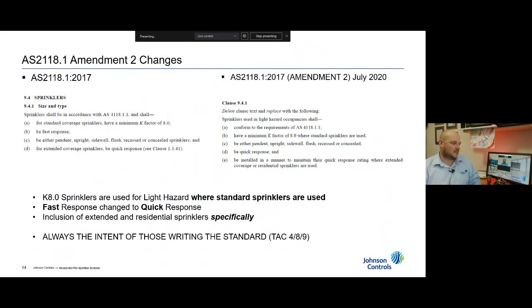So the standard, the 9.4.1 clause changes. Now this has been a little bit of controversy here, because what 9.4.1 says is that for standard coverage sprinklers, they must have a K factor of 8.0, which is our standard commercial sprinkler. And what has happened is a number of people have said, well, if you're going to be using these in a residential application, you can't use residential sprinklers because they have a K factor of 7. That was never the intent of this clause. And so you see on the right hand side there that it has been amended so that they do have a K factor of 8 where standard sprinklers are used. And we've added a paragraph there that says they are to be installed in a manner to maintain the quick response rating where extended coverage or residential sprinklers are used.